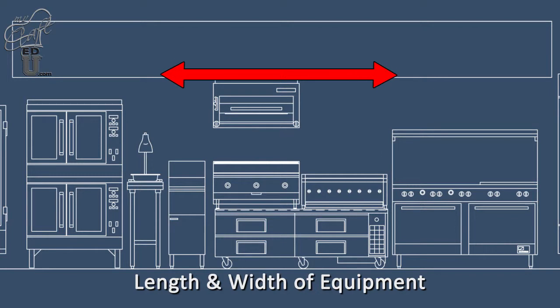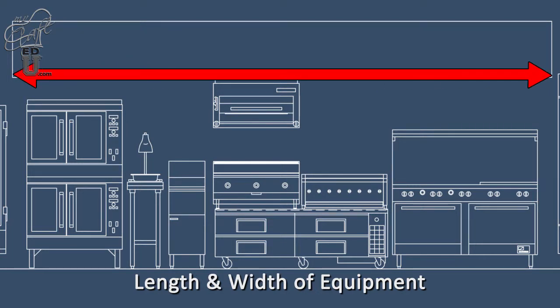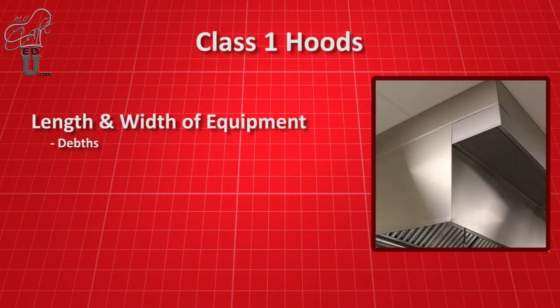The length and width of the canopy is determined by the overall length and width of the equipment under the hood. Exhaust hoods are available in 48-inch, 54-inch, and 60-inch deep. Heights are available in 24-inch and 30-inch tall.